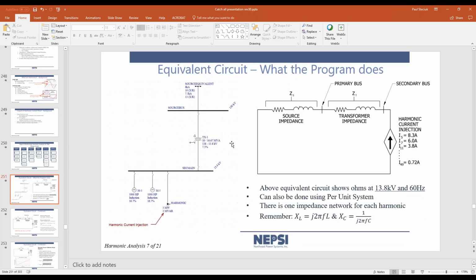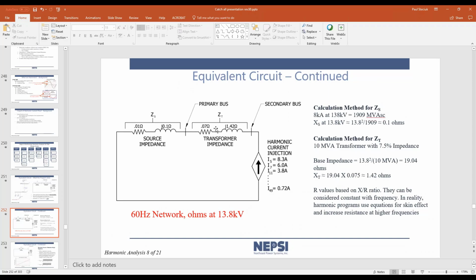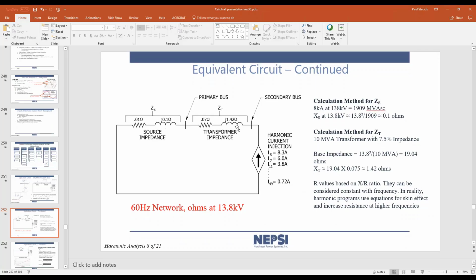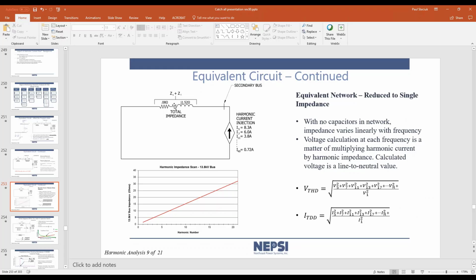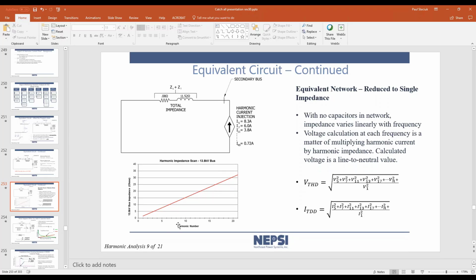So I take this system here and convert to impedance values, and I did it in ohms. You could do it in per unit. The system can boil down to just a single current injection and a single impedance. In such a case, you can inject 1 amp at each frequency and create a plot. If you have 1 amp of injection, you have V equals IR, so R equals V divided by I. If I is 1, the resulting voltage at this point actually represents impedance also. So if you were to do a plot, it would be just a simple linear curve like this. This is harmonic number versus ohms on the axis. So this is the most simple impedance scan that you can have, and it basically says what the impedance is for each harmonic current point on the network.